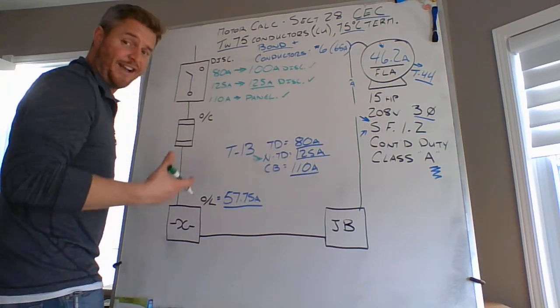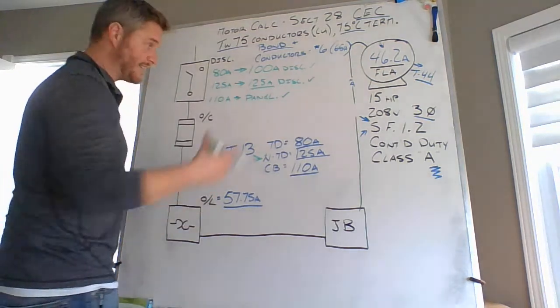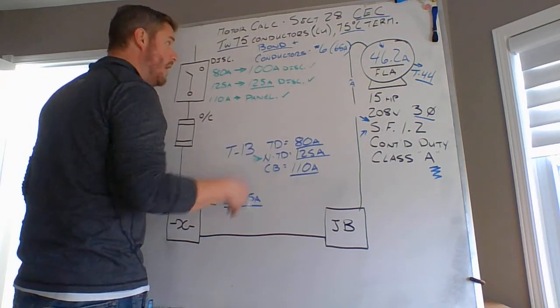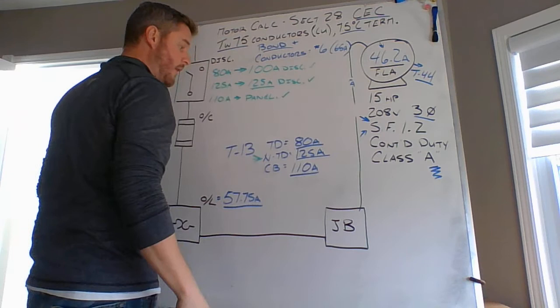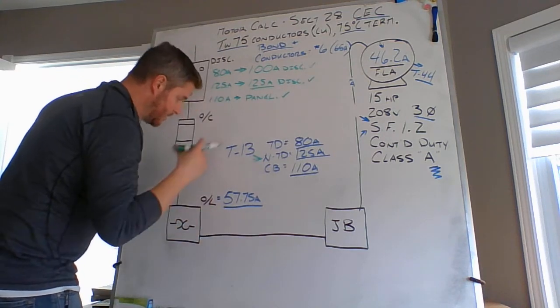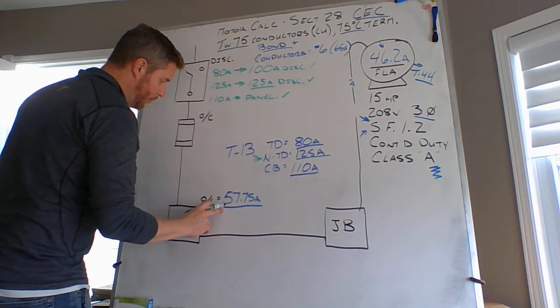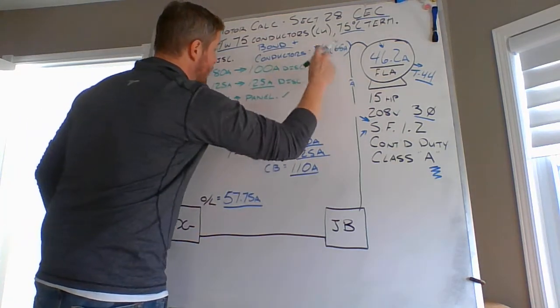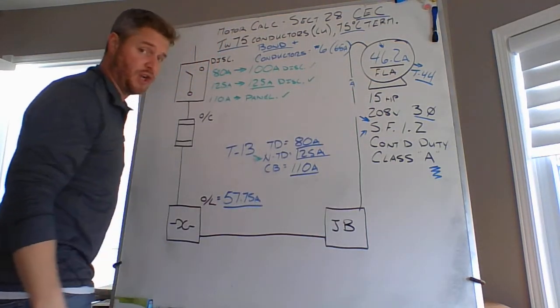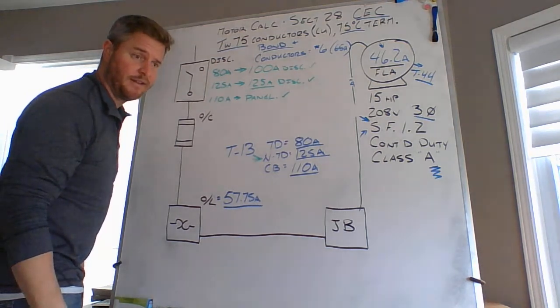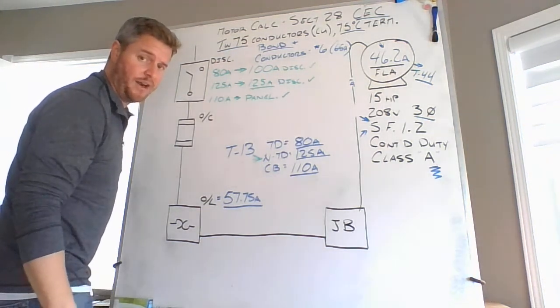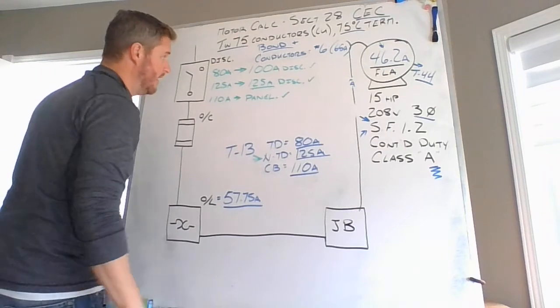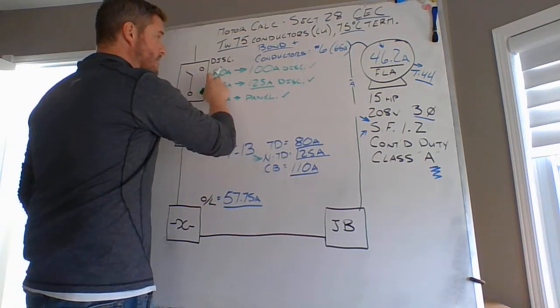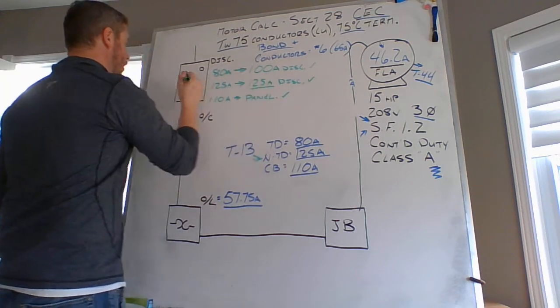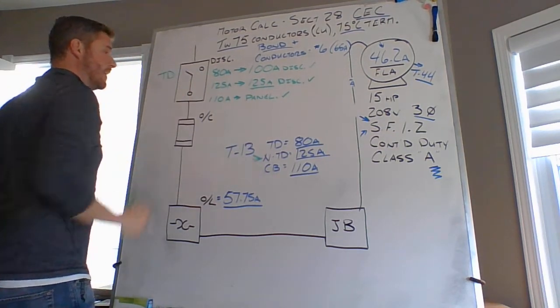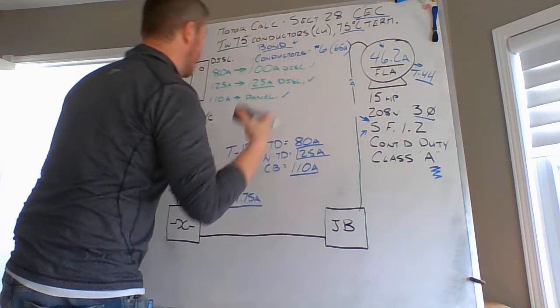Yeah, that's the calculation. Absolutely. That's exactly what we're alluding to this entire time. Your number 6 conductors are good for 65 amps. Their calculated value should never exceed 57.75, and that motor should never draw more than 46.2 amps. So yeah, why not? Let's put in the 80 amp fuse in the 100 amp disconnect and call this a time delay installation. And we'll get rid of the non-time delay thing.